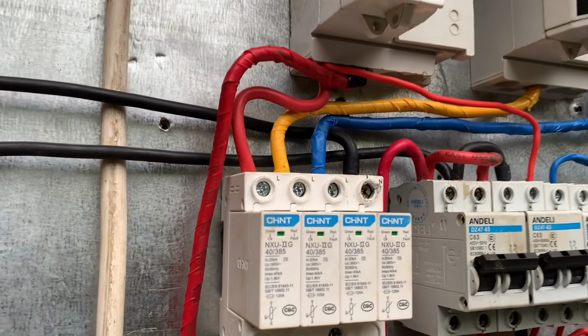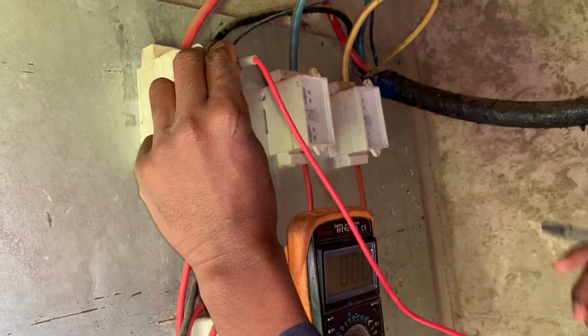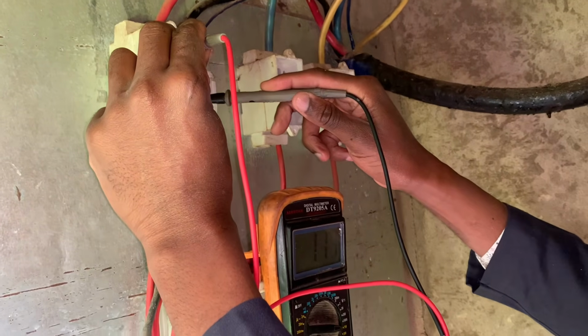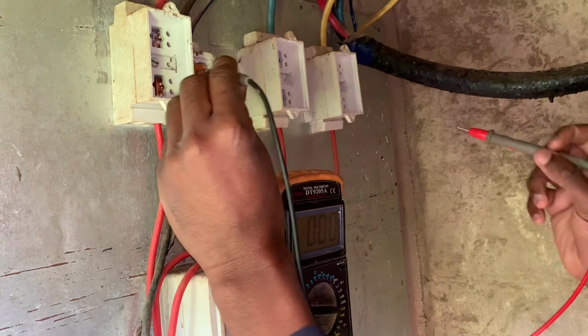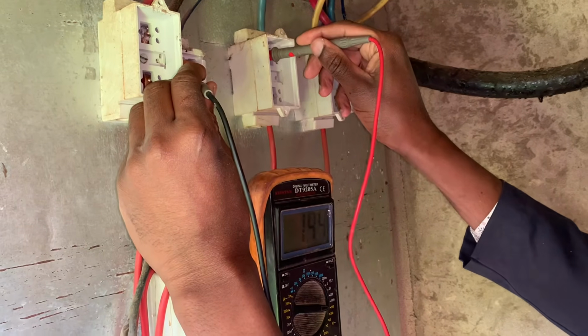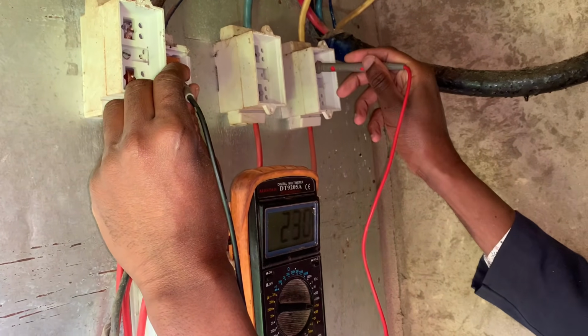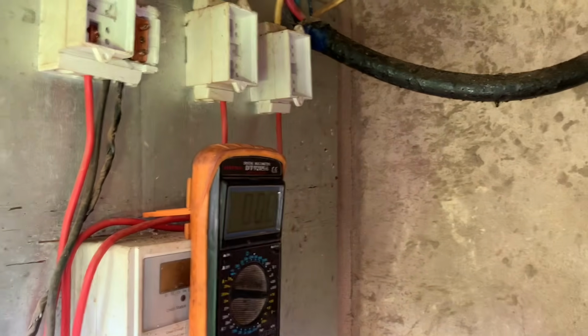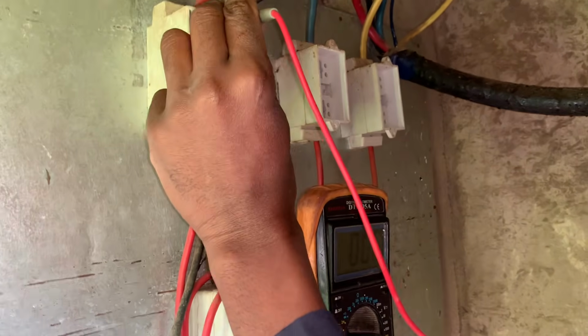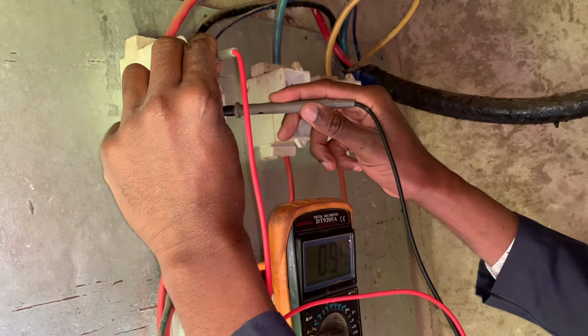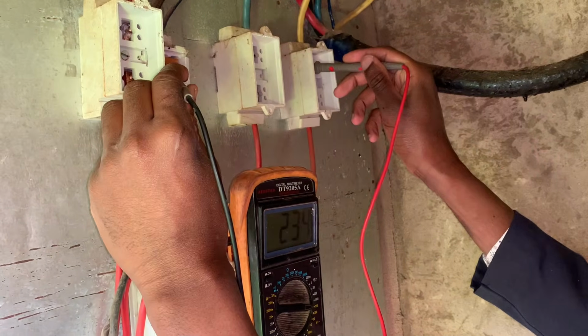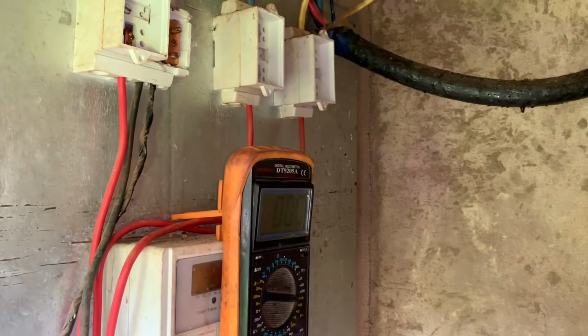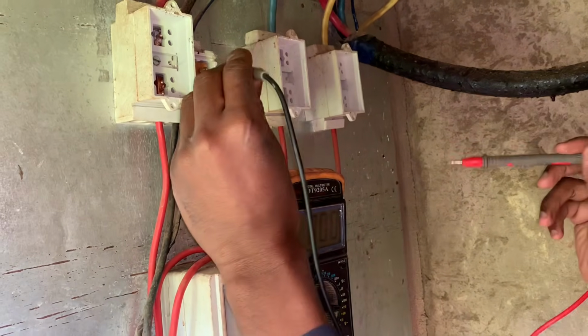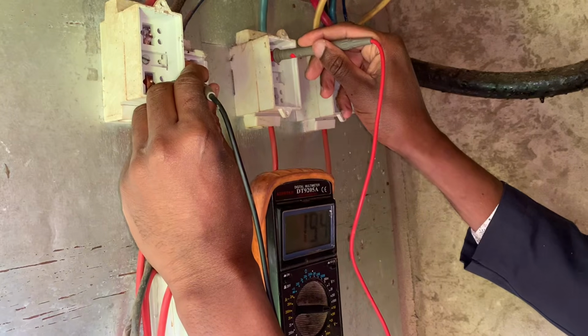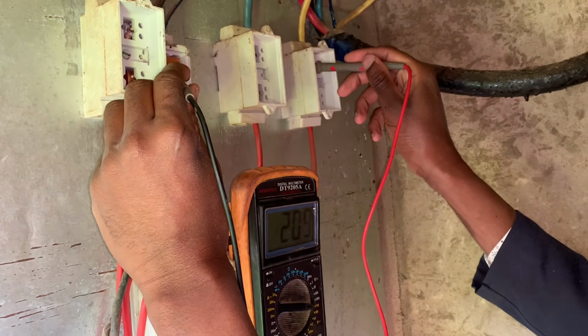It is very important to note that there is a neutral that supplies each and every single phase, in case any of the three phases is chosen for a particular load. Now, the phase has to give a voltage in relation to the neutral because of the return path. If the voltage is 240 for us here in Africa or Kenya, then that is okay. If it gives less than that or above that, there could be an issue that needs some checking.